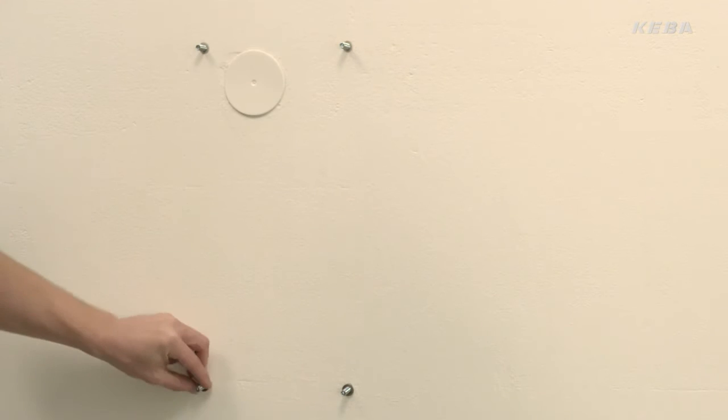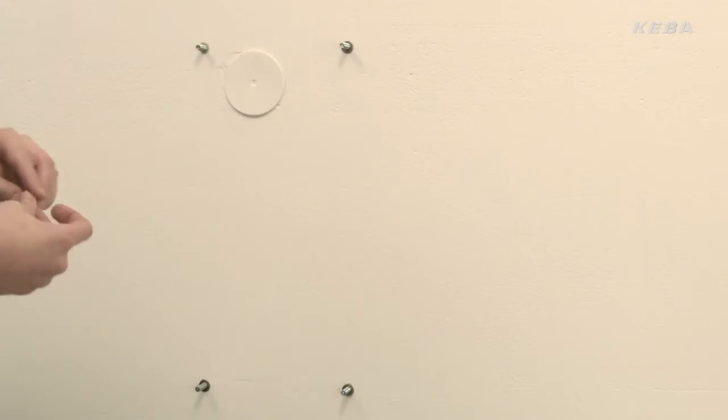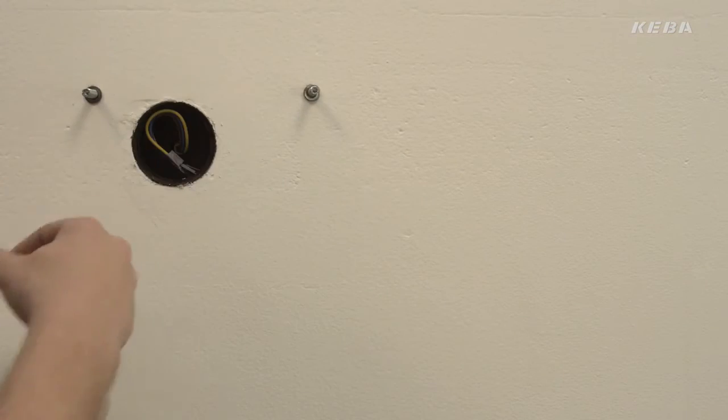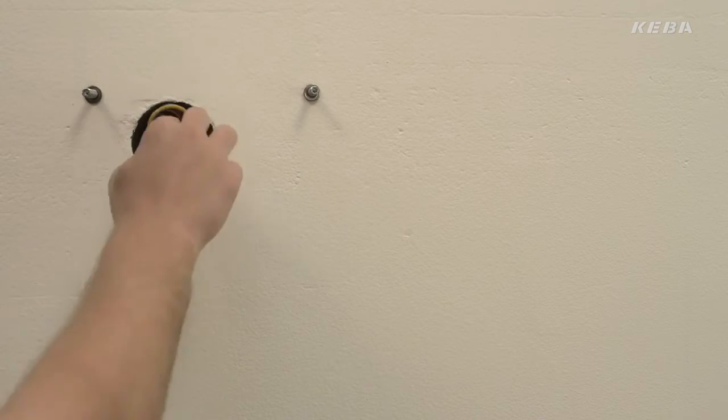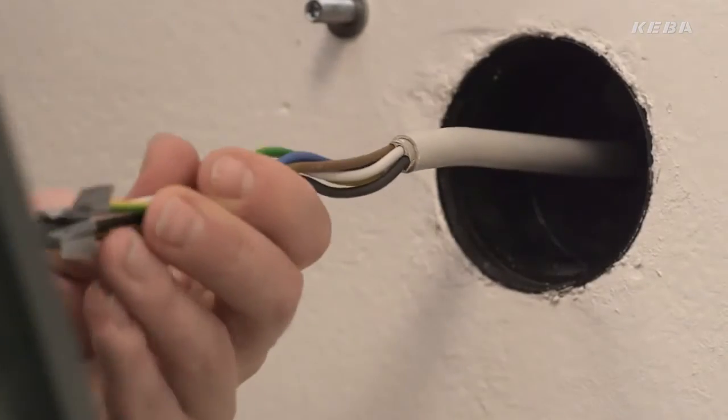For surface mounted installation, use the cable gland supplied. This prevents moisture ingress into the housing in both installation cases. Ensure that the connection cable is not live and that it's secured against being switched on.